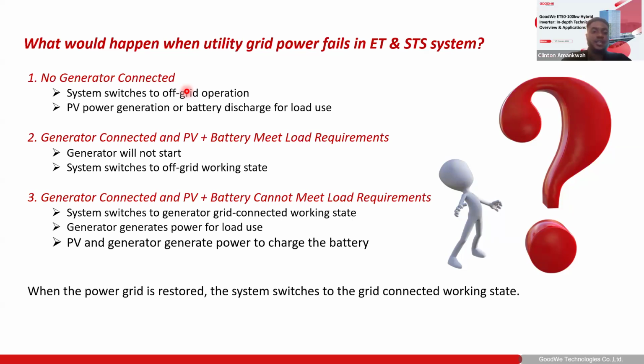Now, the second option is, okay, I have a diesel generator connected. If you have a diesel generator connected and there is a grid outage on site, the first question is: are the PV and battery able to meet the load requirements? If the PV and battery are able to meet the load requirements, the system doesn't start the generator. The generator stays off because the PV and the battery are able to meet the load requirements.